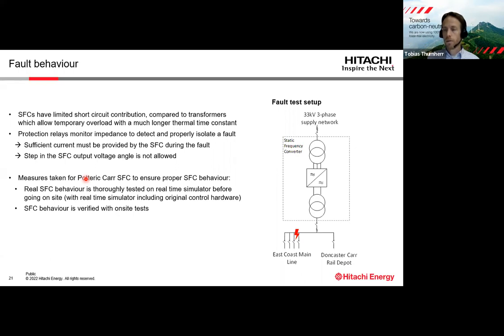Then it's very important with static frequency converter feeding that protection relays operate properly, with this limited short circuit current contribution. Protection relays are set to monitor the impedance, to detect the fault with the measurement of the impedance, and to isolate the fault through that. So this means that the SFC has to provide sufficient current during the fault, and it should not introduce a step in the SFC output voltage when there is a fault.